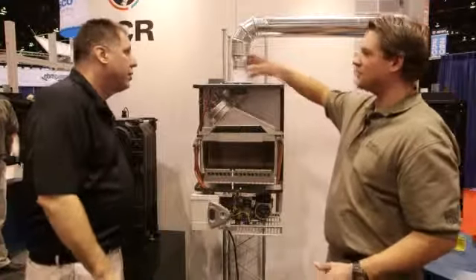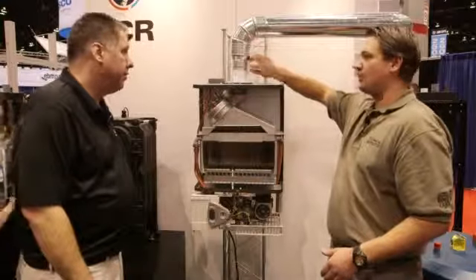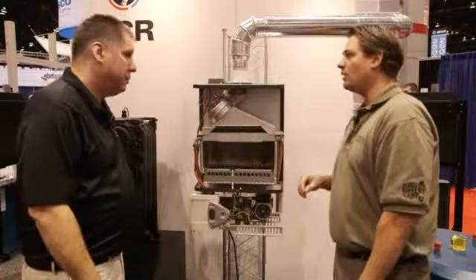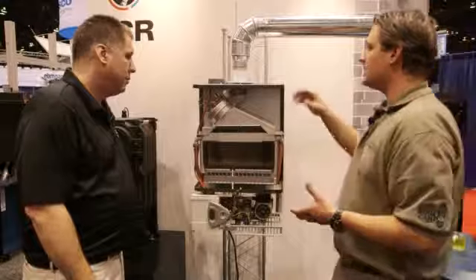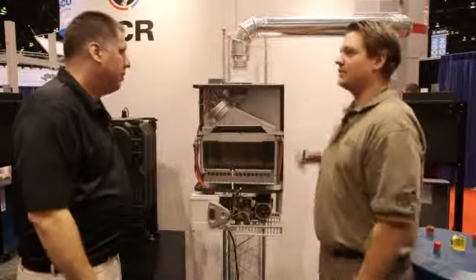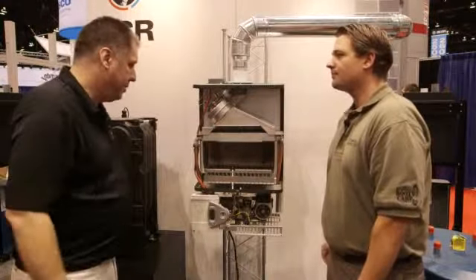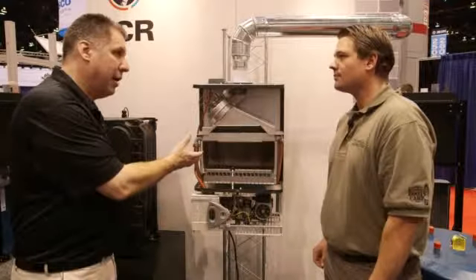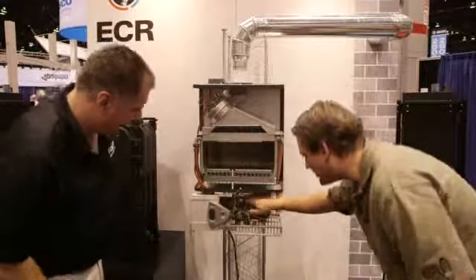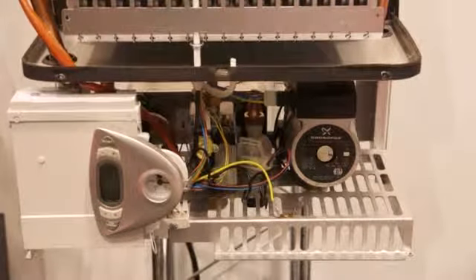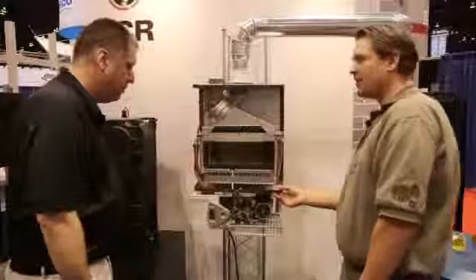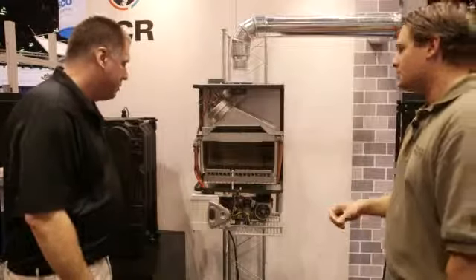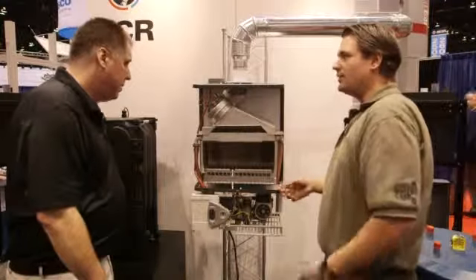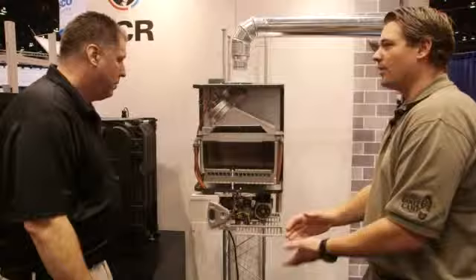What we do is you use the stainless steel venting, and you stay with 3-inch, and you go right out the side wall. It's also sealed combustion, so you can take PVC and run that to the outside and use outside air. Seal it. I got you. And now we can also do domestic hot water with this. It does domestic hot water, and you got your stainless steel brazed plate in the back here. I see that. No condensate drain on this. There's no condensate drain on this. It's 85% efficient, so you're not going to have it condensing. Right. The benefit of that is you don't have to run a drain anywhere. You don't have to worry about that.